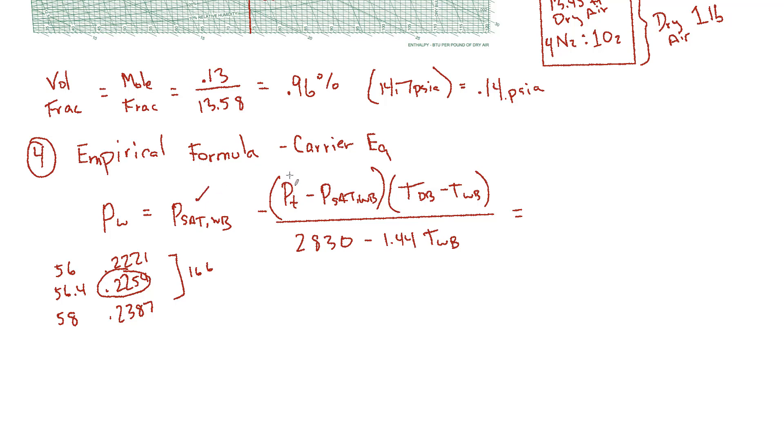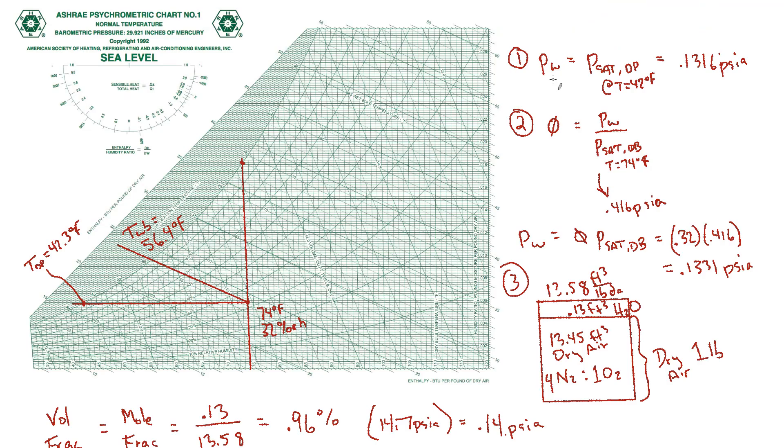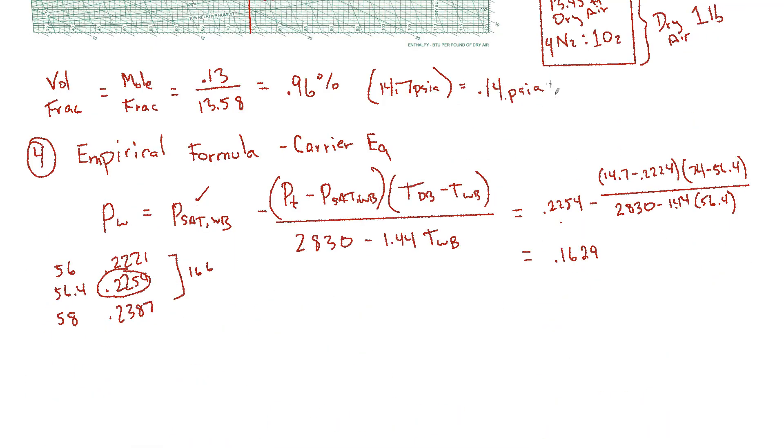The total pressure is atmospheric pressure. So 14.7. Let's go ahead and start plugging some of these numbers in. 0.2254. And I'm going to skip units because it's an empirical formula. 14.7 minus 0.2254 again, times that delta T. The dry bulb is 74. The wet bulb is 56.4. 2830 minus 1.44 times 56.4. That all turns out to be 0.1629, which is a bit higher than what we got on the other methods.